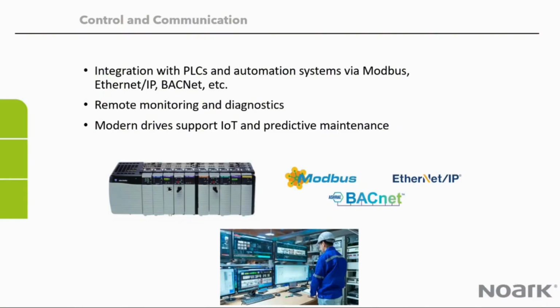Drives are designed to integrate with most of the common industrial automation and building control systems through the available protocols: Modbus, which Keith discussed earlier, Ethernet IP, a Rockwell-based protocol, and BACnet, which is a fairly common building automation system. This would allow you, as Keith indicated, to monitor the status of the drive itself, as well as control, and then allow you to plan predictive maintenance.